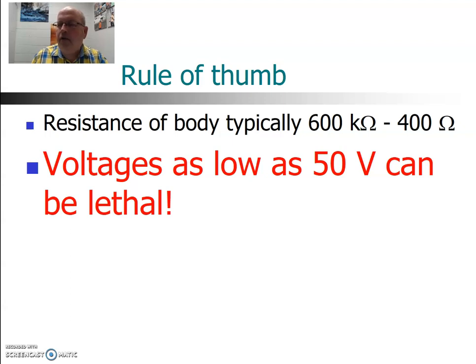So you have to look at the worst case scenario: what's the lowest resistance, and what current can we tolerate? You come up with 50 volts as being something potentially lethal. That doesn't mean a shock at 60 or 75 volts will be fatal, just that given the right circumstances it may be. Be really careful with any voltage greater than 50 volts. Generally, under 50 volts, the current you'd get will be minimal and safe.